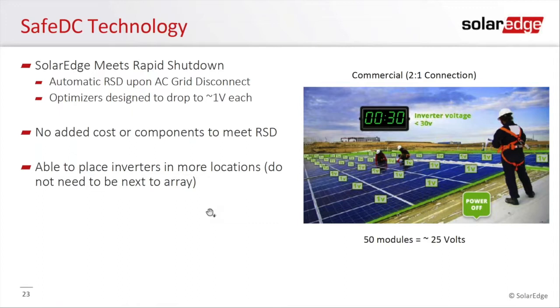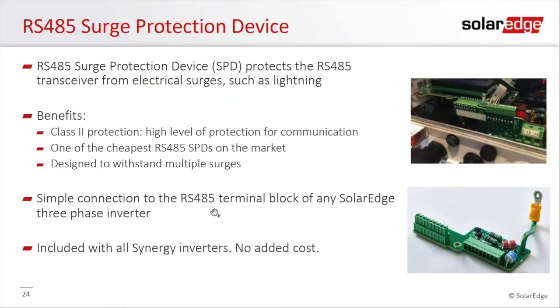So this is really a huge advantage, and I don't want to minimize the importance of this. You really have maximum flexibility on where you could place the inverters. You don't have to put them in the array. You don't have to be within 1 foot of the array. You don't have to be within 10 feet of the array. You really could put the inverter wherever you want, because effectively we're shutting down at the optimizer. So if you want to reduce your cable cost and put your inverter next to your AC interconnection point, you could do that. If you want to put your inverter inside the building or on the side of the building instead of on the roof, you could do that as well, and that will help you with your O&M costs. So that's the Safe DC technology.